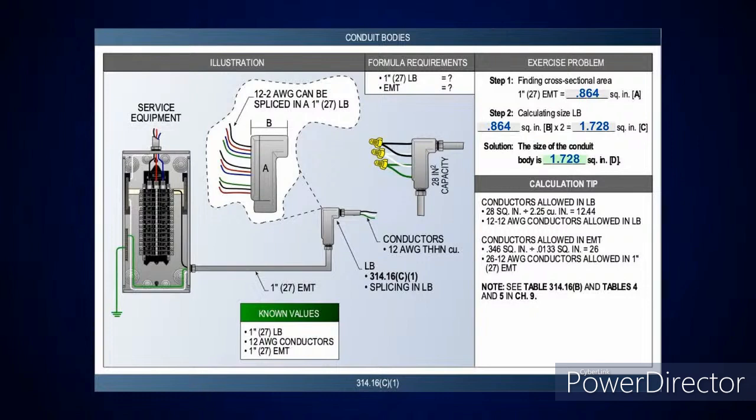You're going to go over to Chapter 9, Table 4. In this case, we're doing EMT and getting the square inch of the EMT, which is 0.864 square inches. Then you just multiply it by two. That'll tell you what you need for making those splices and for the size of that conduit body, which is going to be 1.728 square inches.